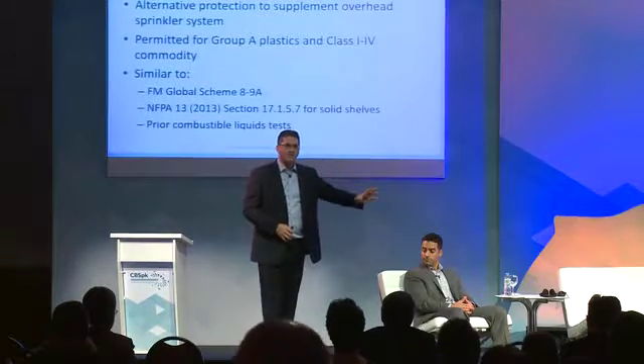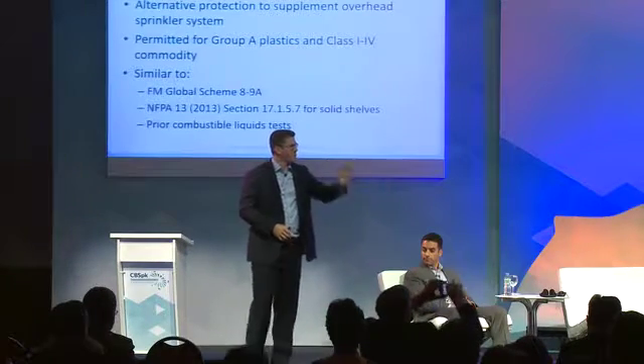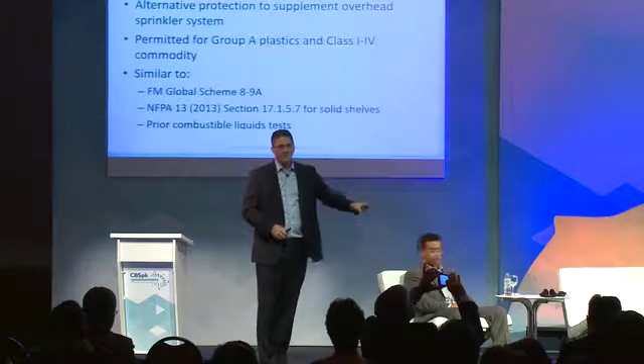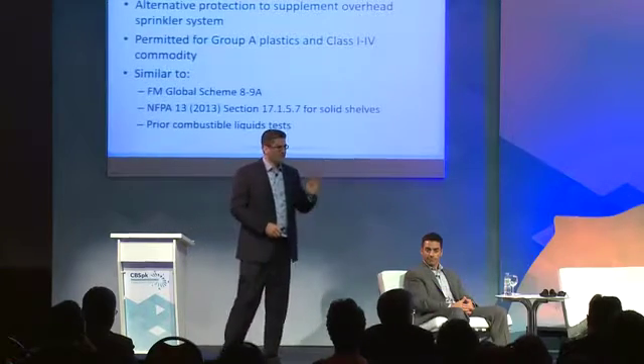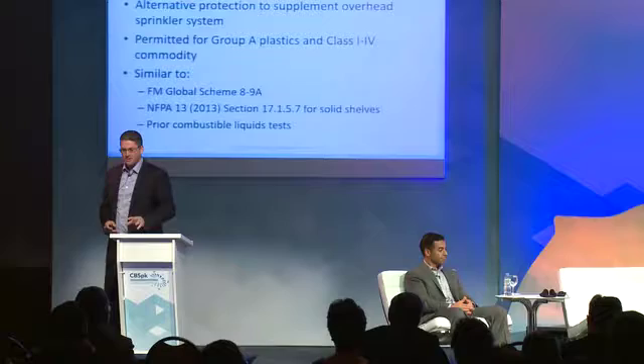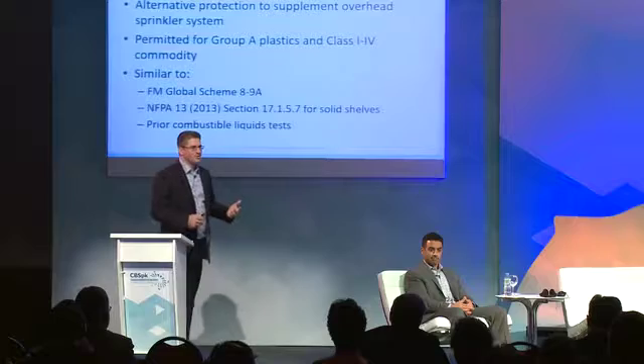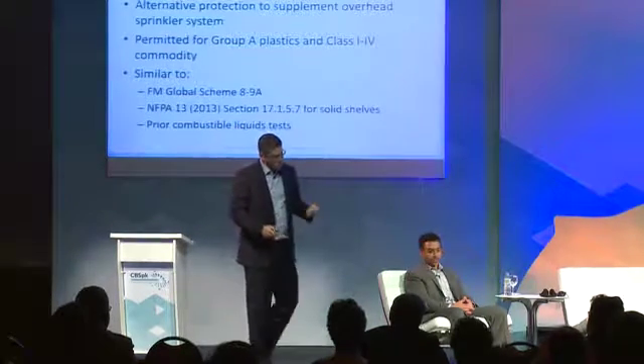So the last criteria I talked about, ceiling-only K25, Carrie is going to tell you for 20 minutes about all the fire testing that was done on that. Fire test after fire test. This criteria, in-racks with horizontal barriers, how many fire tests were submitted for this one? Carrie? Zero. None. The code change was put through based on similar systems that were already in the code and the committee's comfort that, quite frankly, if you put in that many in-rack sprinklers, it's probably going to work.